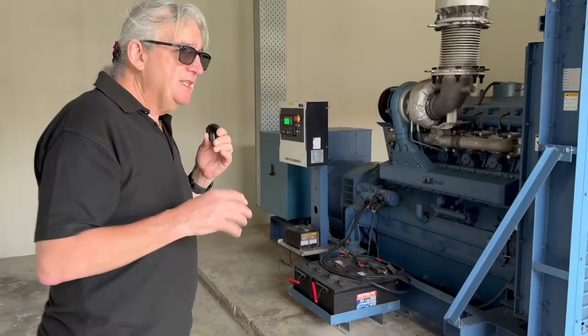We'll keep the genset as an emergency, but we would basically take the AC coming in and feed it into the PCS, which will charge the batteries, connected via transformer. The battery is DC coupled, and the batteries will then DC couple back onto a secondary PCS. On the DC line, we will put the MPPTs - everything will be on there.